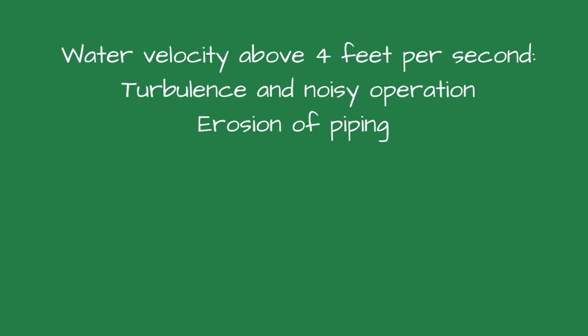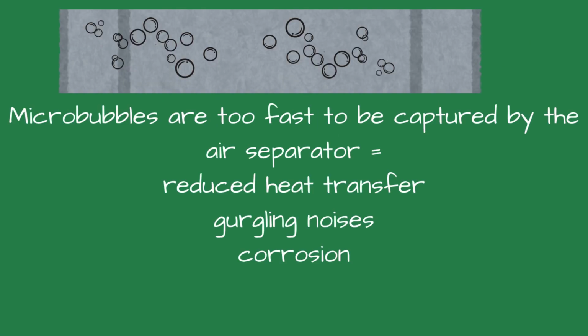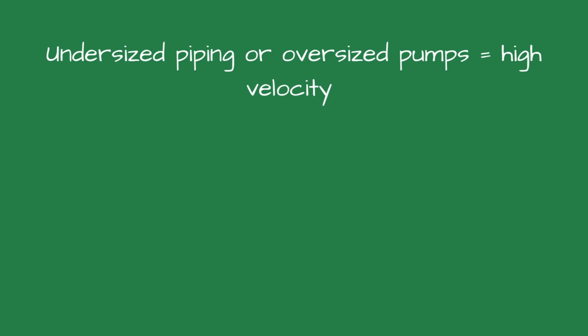Even worse, high velocity can lead to erosion inside the pipes and fittings, especially at elbows or changes in direction, shortening the system's lifespan. High-velocity water can keep microscopic air bubbles suspended in the flow, making it harder for air separators to remove them. Entrained air reduces heat transfer, causes gurgling noises, and accelerates corrosion.